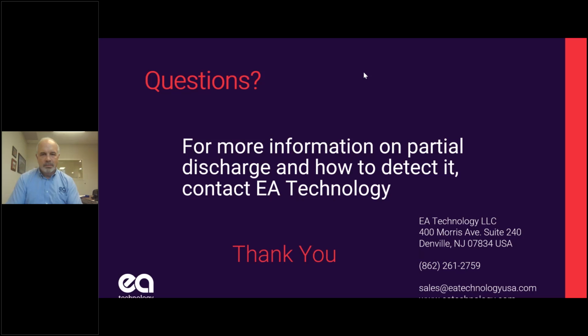Is it better to do online cable testing during high load conditions, peak hours? It doesn't play a big part, because partial discharge is a voltage phenomenon, not a current phenomenon. So when you have higher system voltages, you're more likely to have PD. But if your system voltage isn't varying much, it doesn't make much difference, with the exception of high load causing thermal expansion and potentially causing cracks to be more visible. But that's not that common. So I would not say that you really ought to test at high load.